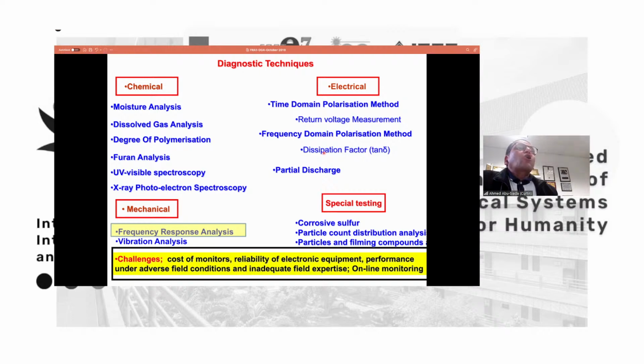A common challenge now in all of these techniques is the cost of monitoring. Some of these techniques are very expensive, and there's the reliability of electronic equipment to consider. You have some sensors that you should connect to the transformer in harsh environmental and operating conditions, with very heavy electromagnetic fields in the substation, background noise, and high voltage. So how can we assure and guarantee the reliability and accuracy of the equipment and sensors we are using, and the performance of the sensor under such harsh environments?